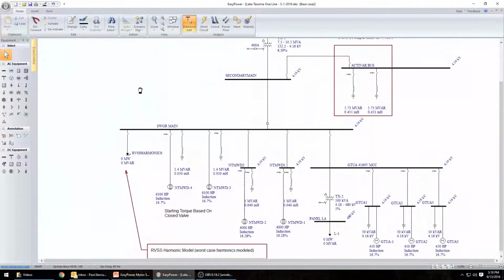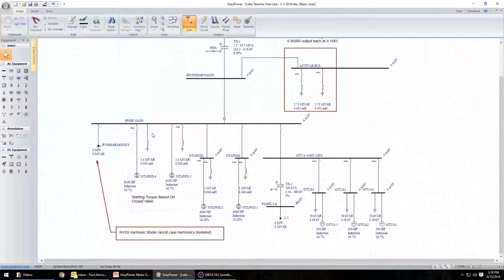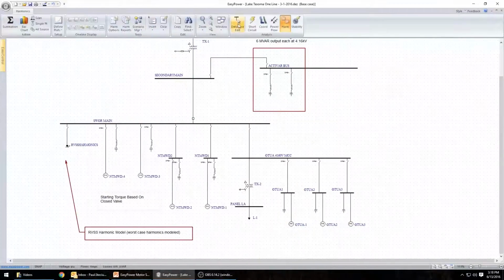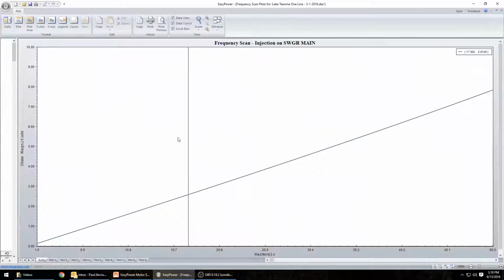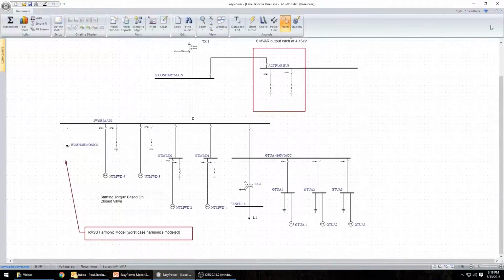From a harmonic analysis standpoint, we of course are, as mentioned, worried about the harmonics produced by the soft starts. So if we go into harmonics mode, right now we have all the capacitors off here. We have these capacitors off here. We can turn this capacitor off here associated with that motor starter, and then we also have the actiVAR offline. So in this situation, it should be just a straight impedance as we have shown here, because there is no capacitance modeled. Therefore, it should be just a straight line impedance.